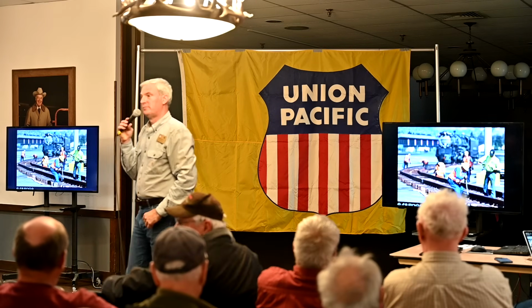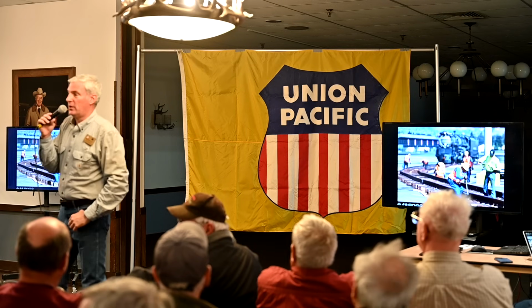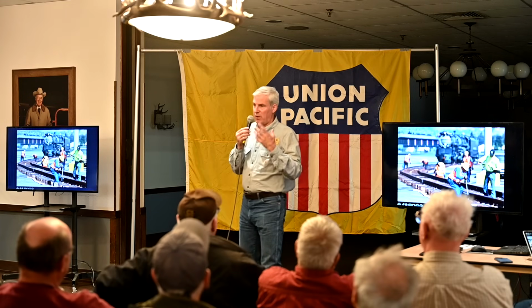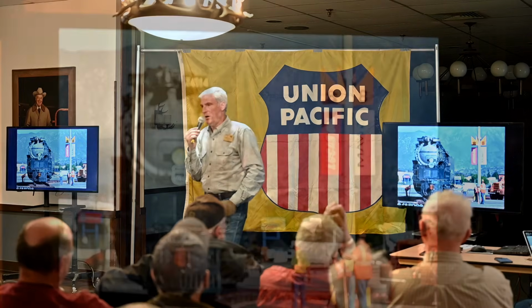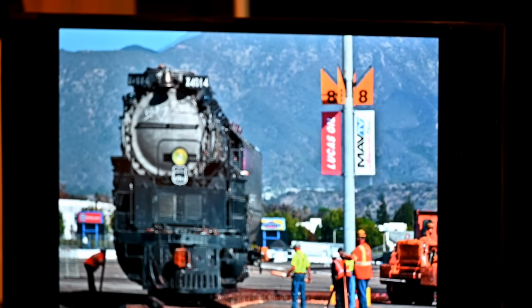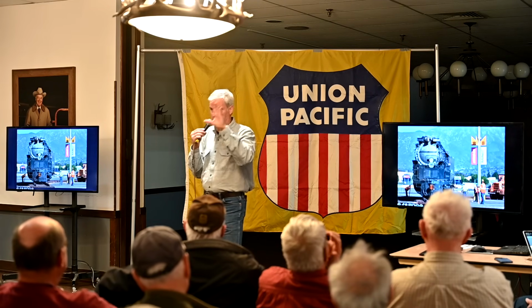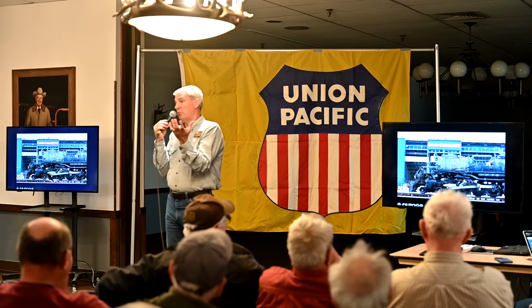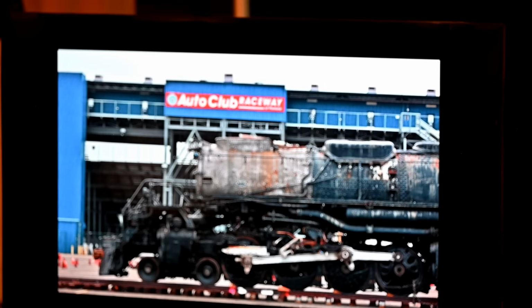Yes, Matt from Australia. Question on hydrostatic testing. Can you just talk through what you do for a hydrostatic test? Like what pressure and how long? Well, in America, we're required in our locomotive to run it to 375, so 125% of its maximum allowable working pressure. There's no time component with that. We run it to that hydraulic pressure and hold it there, the inspectors are with us, and we run through a series of evaluations of the critical structure, all of it. We're looking at everything from the superheaters on. The jacket is on it most of the time, but when we're doing a 1472, which is our very thorough boiler survey, the jacket is off of it.